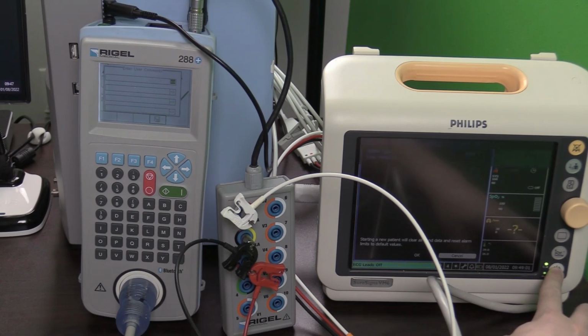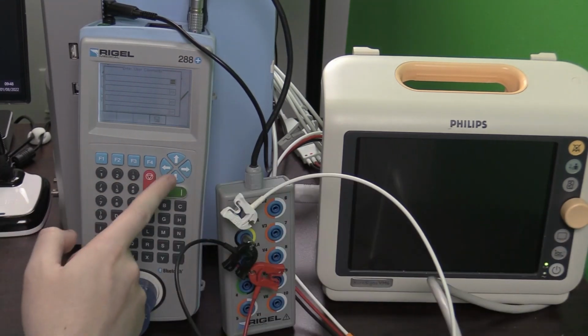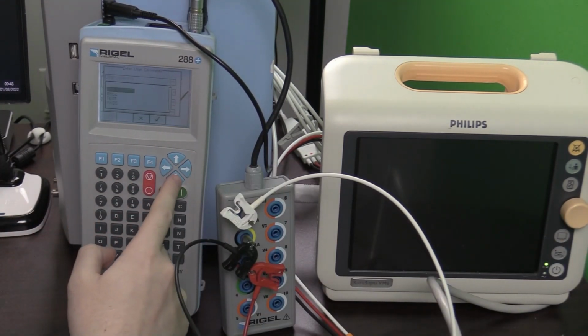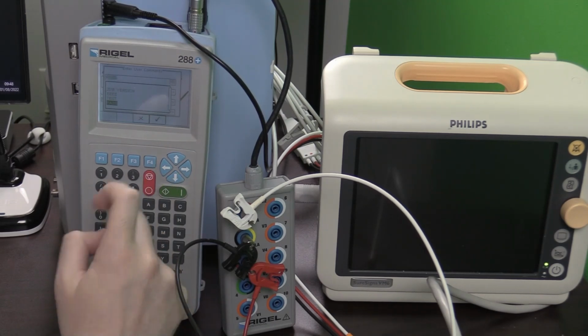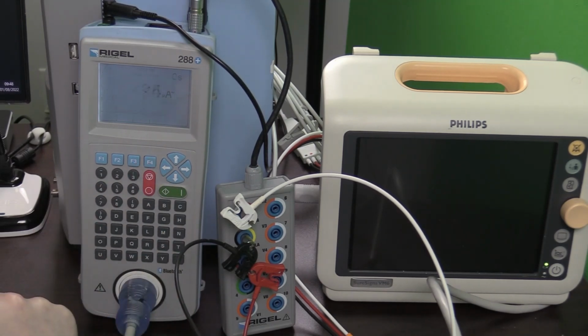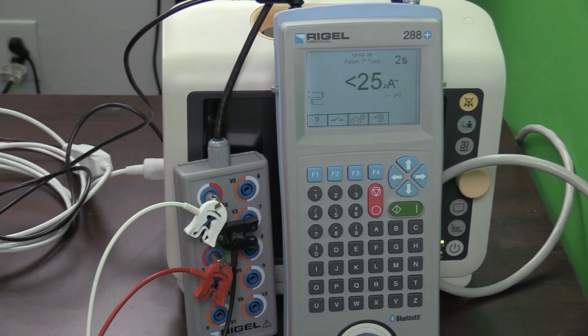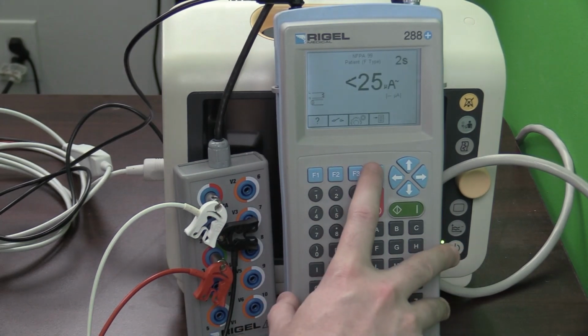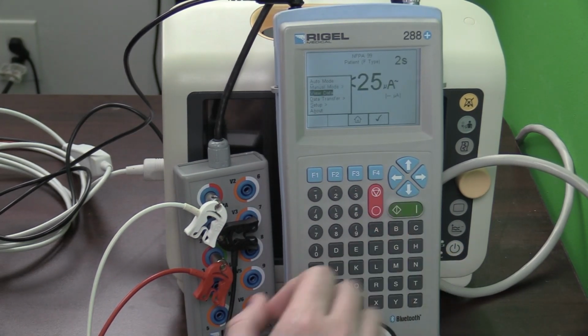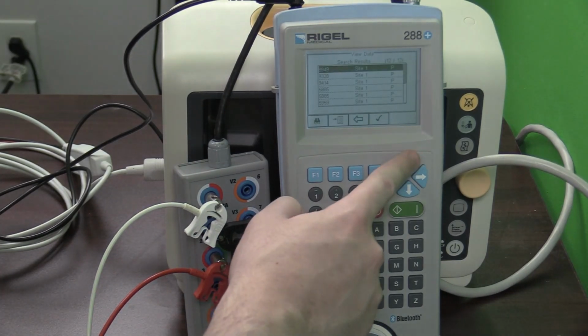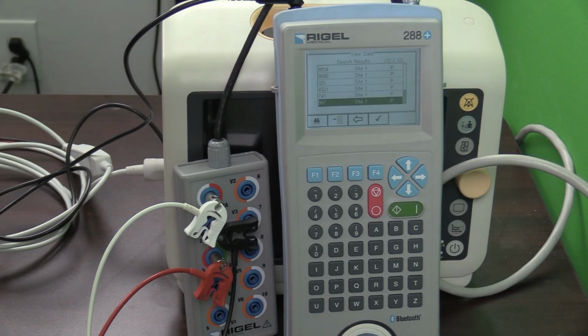Once you get to this screen, that means the test is complete and you can input anything you want. It's passed the test, so I put that it is passed the test and select F4 to save the data. Now that the test is complete, you can go into the unit and view the test results. So you're going to select F4, go down to View Data, and select F4. And it's always going to be at the bottom of the list.